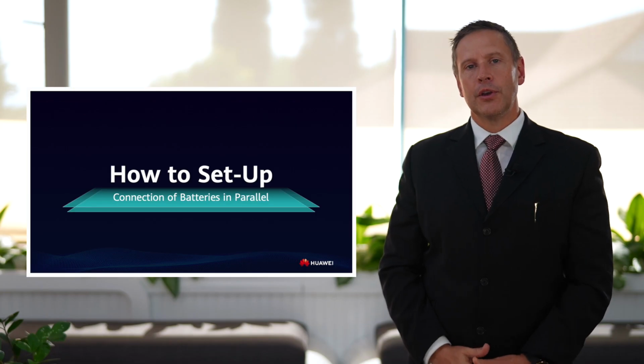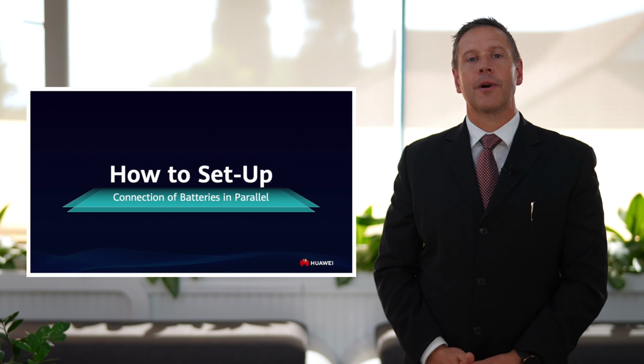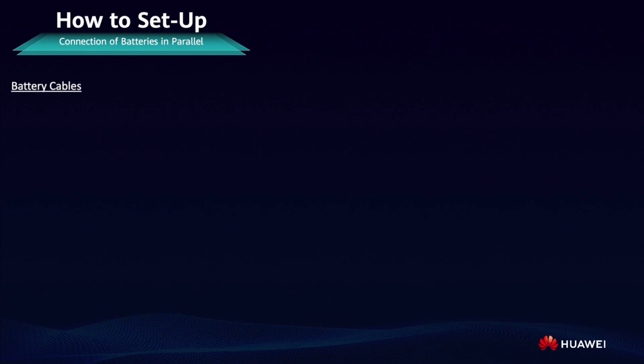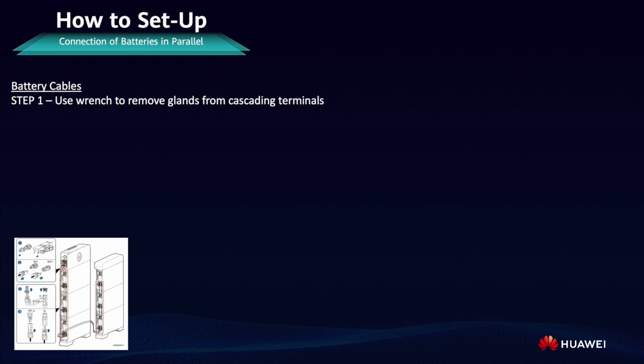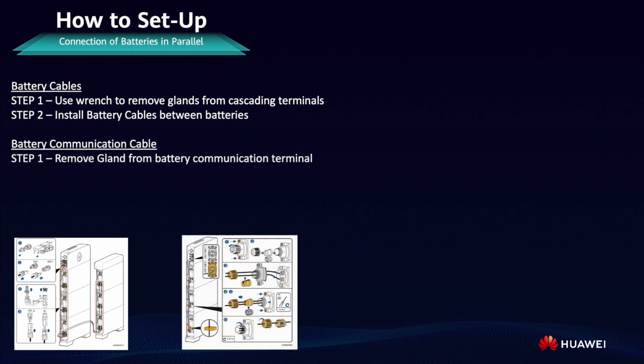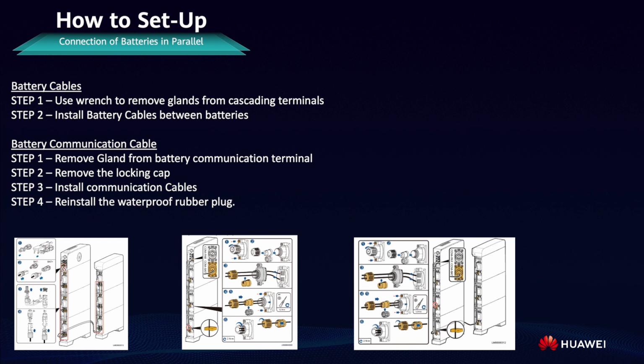How to set up. Connection of batteries in parallel. Battery cables. Step 1. Use wrench to remove glands from cascading terminals. Step 2. Install battery cables between batteries. Battery communication cable. Step 1. Remove gland from battery communication terminal. Step 2. Remove the locking cap. Step 3. Install the communication cables. Reinstall the waterproof rubber plug. Install communication cable for battery modules in sequence.